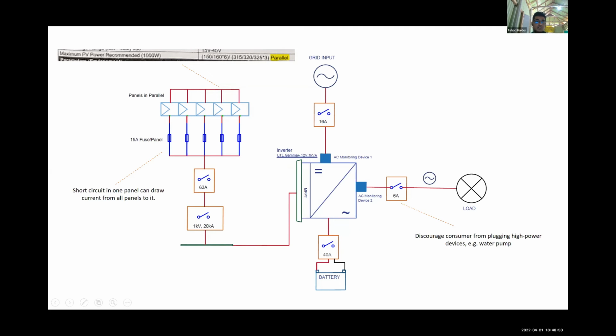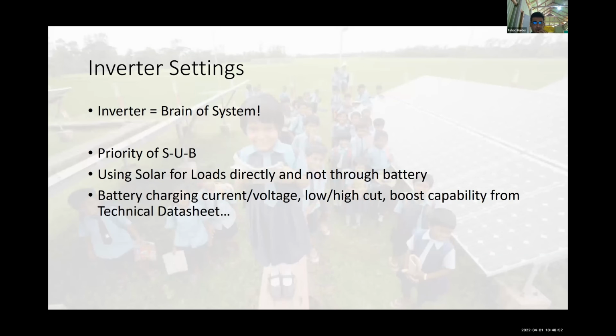So I've been talking about the inverter a fair bit. Why? Because the inverter is basically the brain of the system. It decides what energy to use and where it goes, basically. So the priority of the inverter, according to the Bangladeshi setting, the rural Bangladesh setting, I reckon the priority is SUB - so that's solar, then utility, then battery.